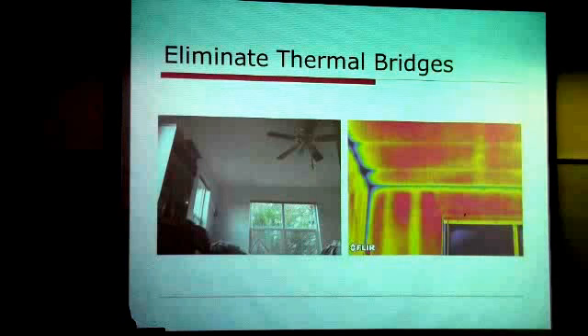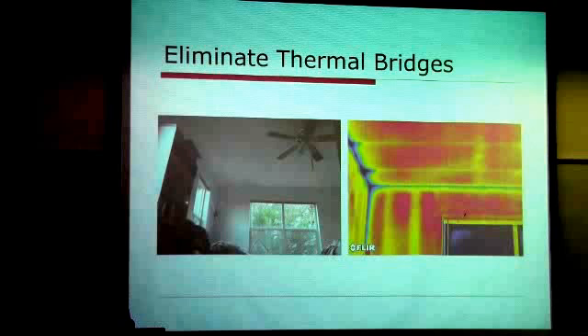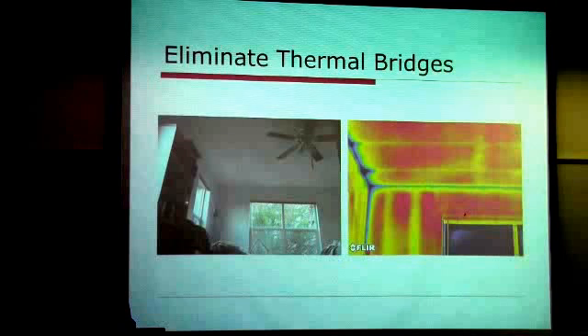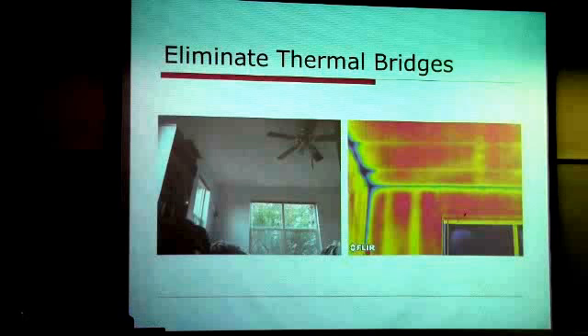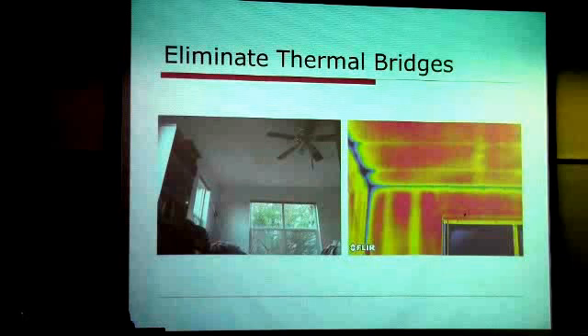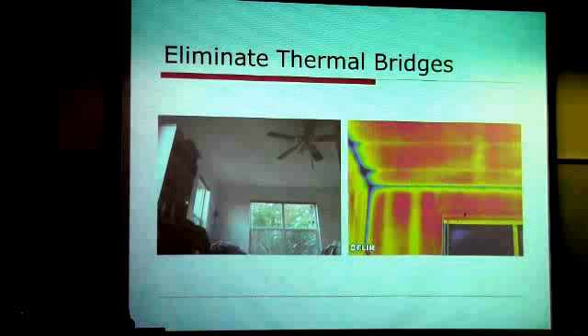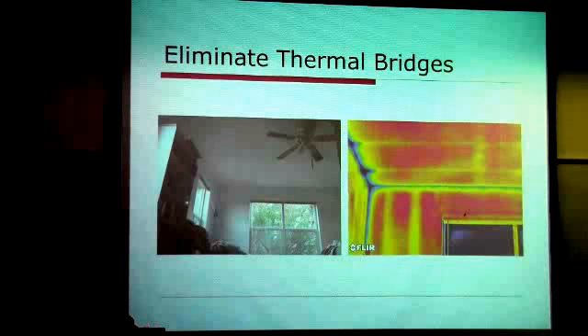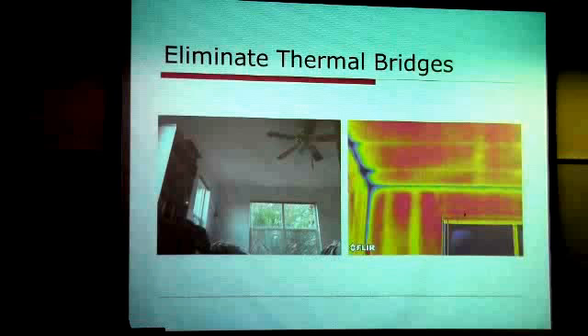Do you have to leave fans on for extended periods of time to get all the moisture from the showers? Yeah, these systems we're talking about run continuously. Oh, okay. But they're only using 30 watts of power, so less than a kilowatt hour a day, which would be about 8 cents, somewhere in the 800 watt hour per day range.